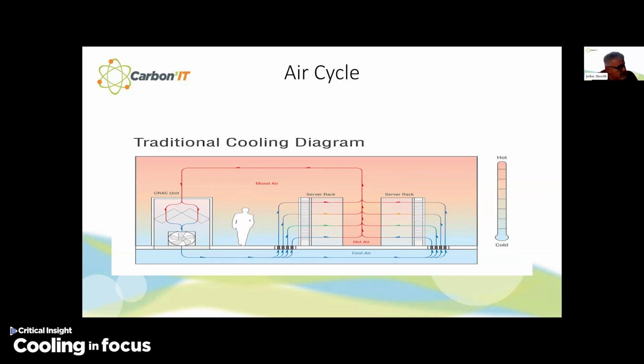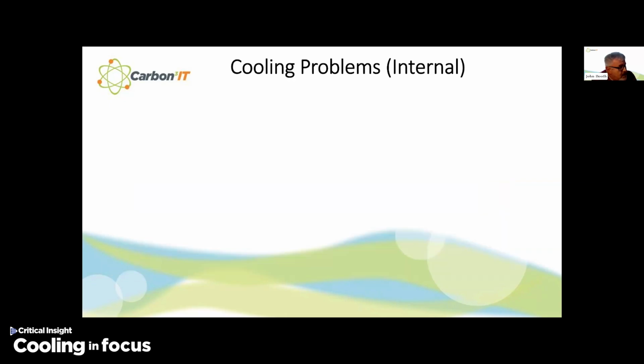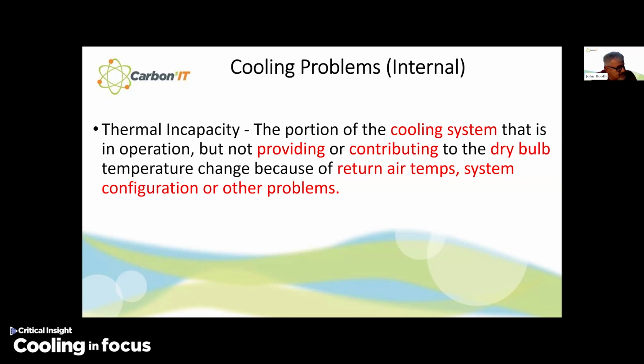So in a conventional air cycle, we have cold air that's coming out of the CRAC unit into the raised floor. We bring it up through tiles. It's drawn in through the integral fans through the servers, gets heated up, and then the hot air rises, basic physics lesson, and then we direct it back into the top of the CRAC unit, and then it passes across the coils. The waste heat goes outside and is dealt with somewhere else, and then we've got cold air now, and we push that back under the tiles again. And that's all very well defined. A lot of people know that, although I have been on sites where I ask them about the air cycle and I get a blank stare. So the problem is that we get thermal incapacity, and that's the portion of the cooling system that's in operation but not providing or contributing to the dry bulb temperature change because of return air temperatures, system configuration, or other problems. Bypass air, for instance, and also recirculation air.